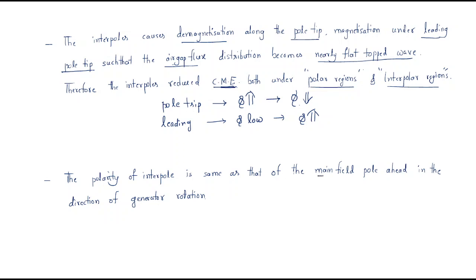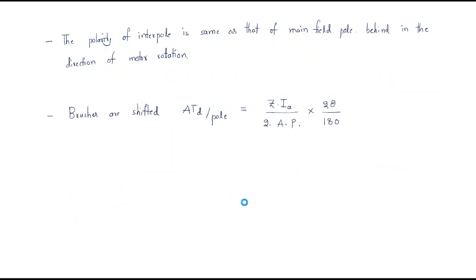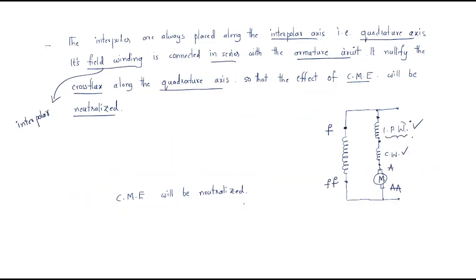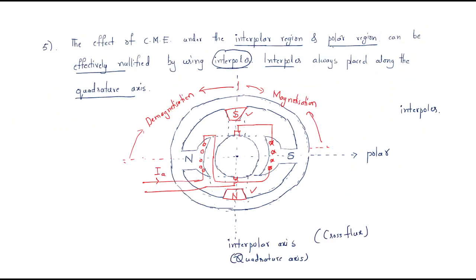The polarity of the interpole is the same as that of the main field pole ahead in the direction of generator rotation. If the main field poles are ahead in the direction of generator rotation, the north pole is here and the south pole is here. This completes the session on remedies of cross-magnetizing effect.